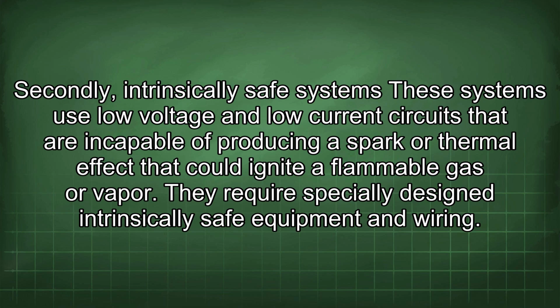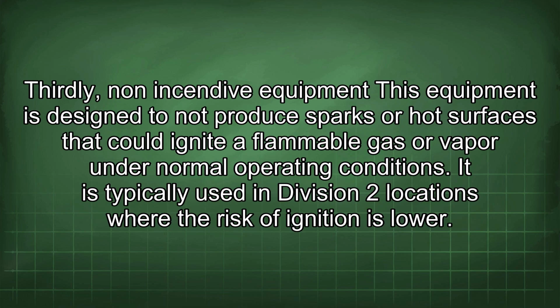They require specially designed intrinsically safe equipment and wiring. Thirdly, non-incendive equipment. This equipment is designed to not produce sparks or hot surfaces that could ignite a flammable gas or vapor under normal operating conditions. It is typically used in Division 2 locations where the risk of ignition is lower.